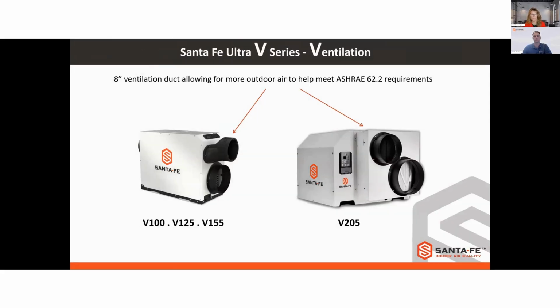So why the V? The Santa Fe V series, the V stands for ventilation. We have actually incorporated into these new units an 8-inch ventilation duct, allowing us to bring in more outdoor air in order to meet 62.2 requirements. So you can see on the left side here with the V100, 125, and 155, we've got that 8-inch duct up on top. And then on the V205, it's on the top off a little bit to the left. And we're going to dive in later to why we really need those 8-inch ventilation ducts.